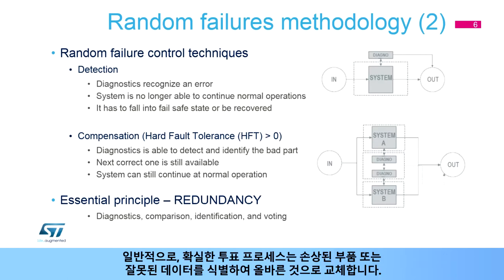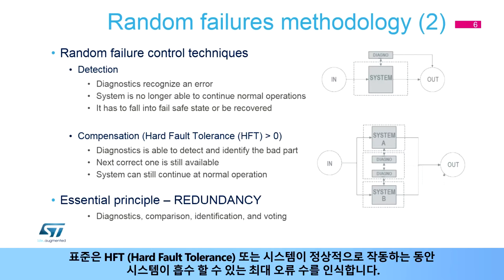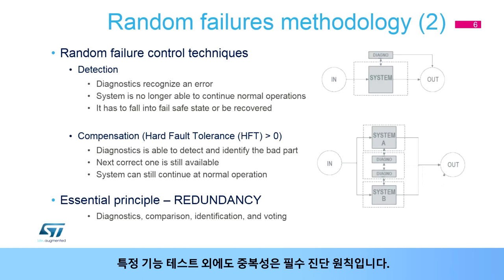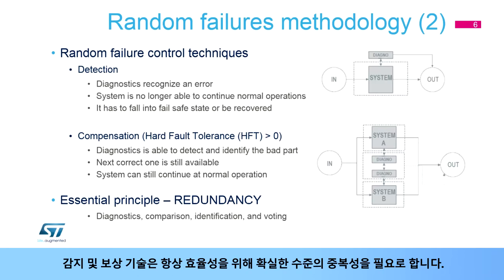Generally, a voting process is used to identify the damaged part or incorrect data, which is then replaced by the correct one. Standards recognize hard fault tolerance, or the maximum number of errors which a system can absorb while it can still continue at normal operation. In addition to specific functional testing, redundancy is the essential diagnostic principle here. Both detection and compensation techniques always require a sure level of redundancy to be efficient.